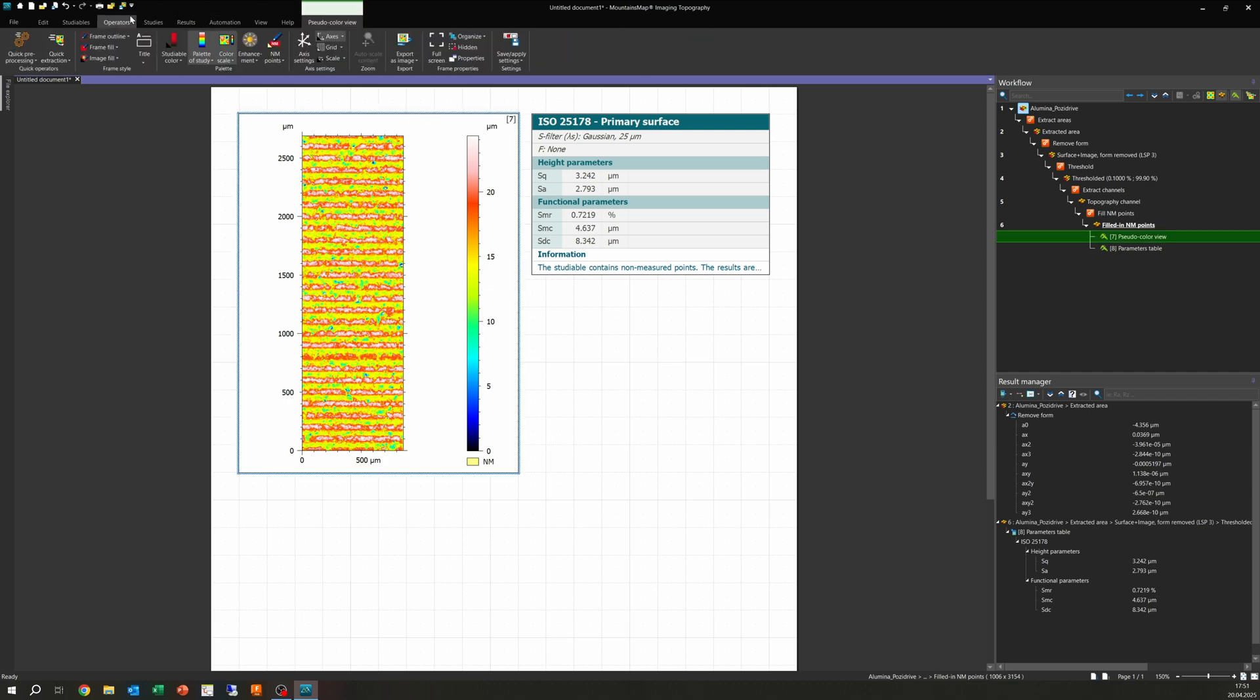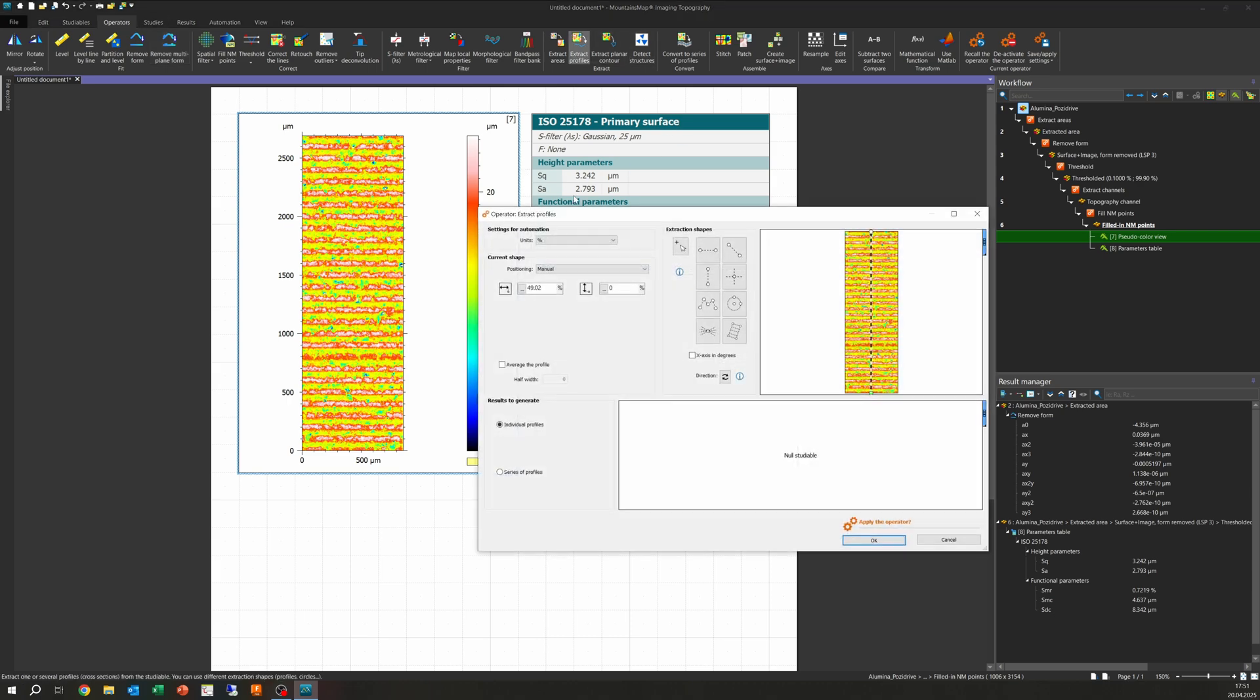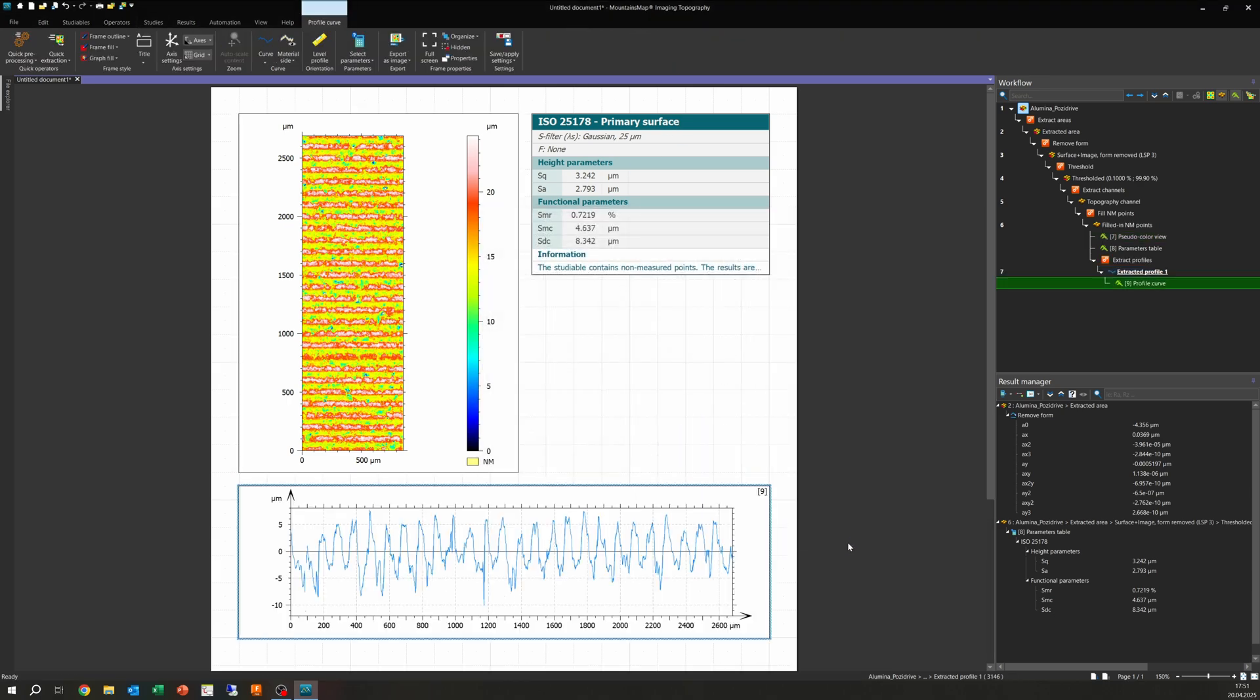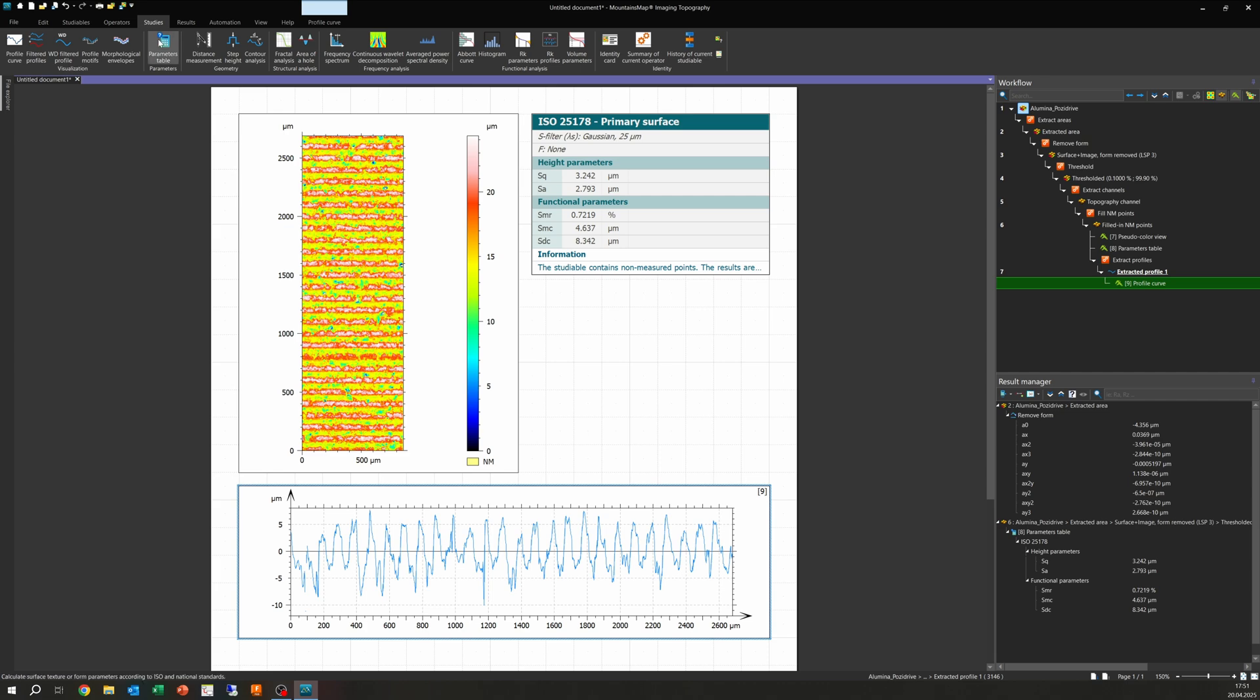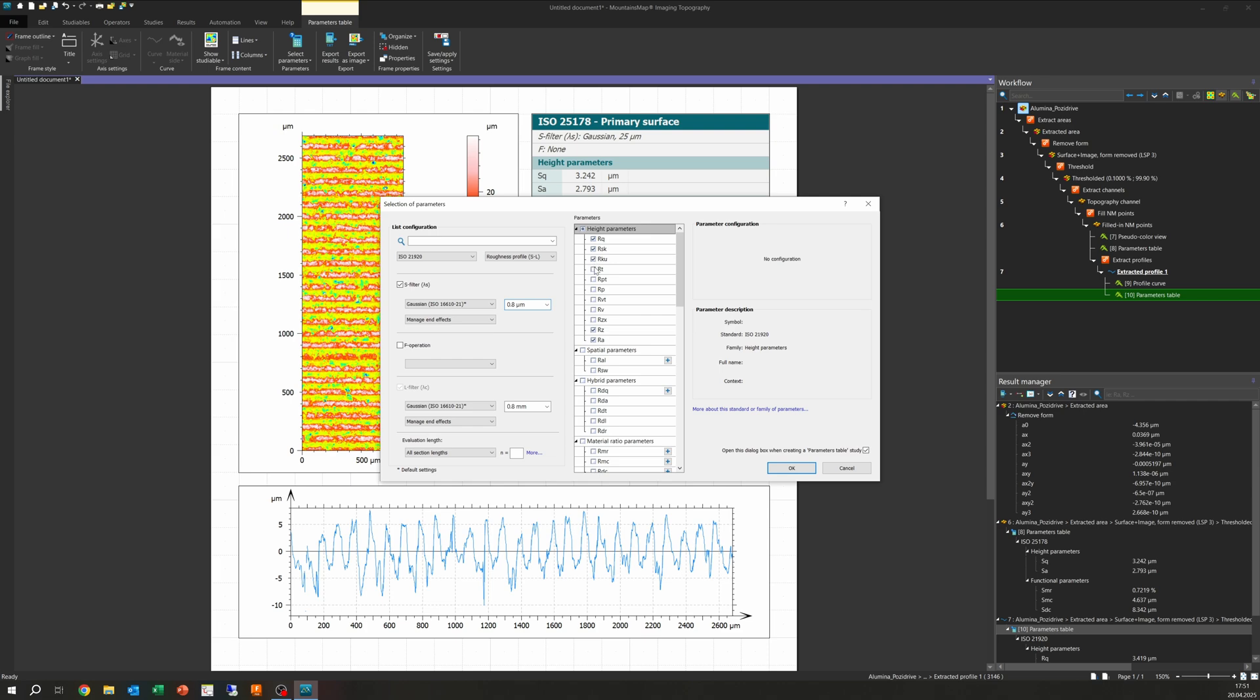I prefer to use areal surface parameters, as they are not dependent on the measurement direction, and more robust, which means more honest than line profile surface roughness. To show you the difference, we are extracting two profiles here, a north-south and an east-west profile. Besides not having the standardized length, you will see a massive difference in the resulting roughness.